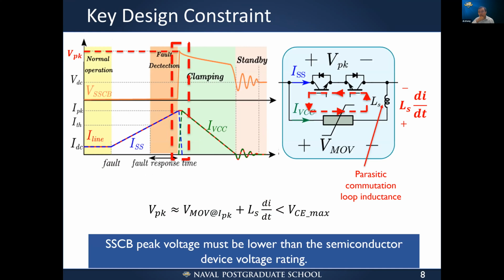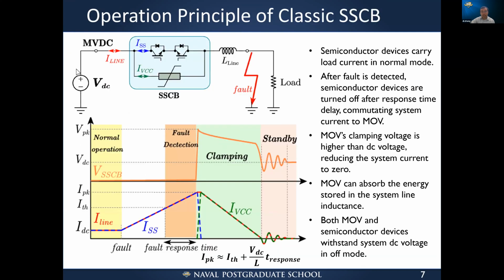So before we talk about the proposed solutions from the teams, let's have a quick review of the operation principles of classic solid state circuit breakers. This is a single line diagram of a medium voltage DC system, right? It has a medium voltage DC source, a solid state circuit breaker, inductance, and also a load. The structure of the solid state circuit breaker is actually quite simple. It has 2 components. One is semiconductor devices that can block bipolar voltage and carry bidirectional currents. And the other is a component that can absorb the energy in the system, typically an MOV.